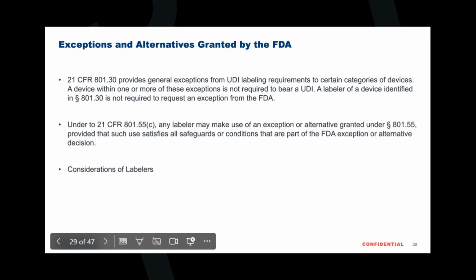Under 21 CFR 801.55(c), the FDA will consider granting requests for an exception from a UDI requirement if the requirement is not technologically feasible. We expect such situations will be rare. The FDA does not consider exception requests that are based on reasons other than technological infeasibility, including but not limited to a financial burden or claims of few or no adverse events. Labeler considerations are in order to establish a system to adequately identify medical devices through distribution and use. The FDA expects that the labels of almost all devices are capable of bearing, and should in fact bear, a UDI on the label unless excepted.